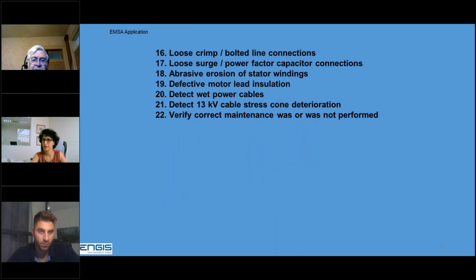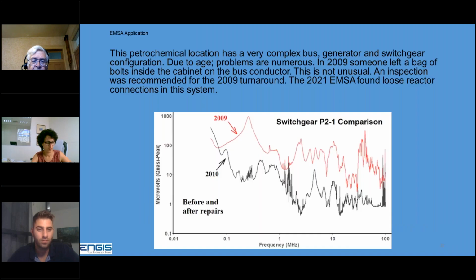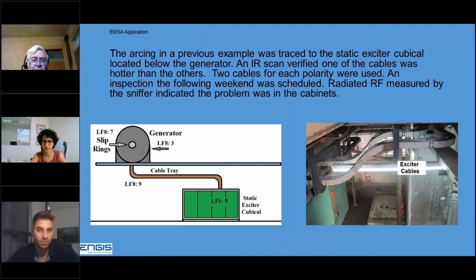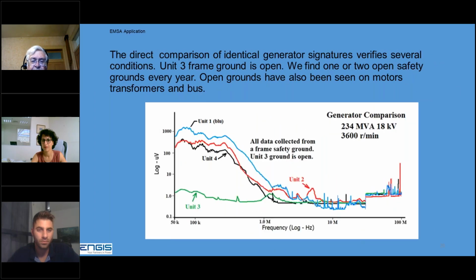You mean partial discharge or EMI? Yeah, the partial discharge, of course. Partial discharge analysis, PDA, was developed in Canada in the 70s, and it was focused on looking for stator problems on large hydro generators. At that time, Greg Stone worked with Ontario Hydro, and then he formed IRIS. And the PD analysis looks at the higher frequencies. It looks for slot discharges, and it's a very good technology if you want to look at the generator only, okay? And it works quite well for finding partial discharges in stators.